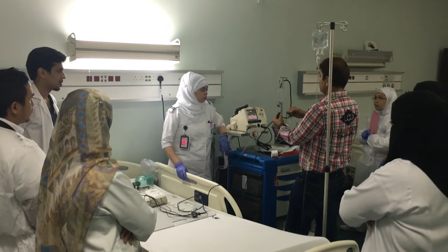To insert it maybe is okay, but to remove it, if somebody doesn't know, you will pull it and it will break, because there is a lock here to remove it. So why are we keeping it, if we are allowed to use the machine only in AED mode, why are we inserting this one? Leave this always, 24 hours, connected. This is the important thing which I have discussed there. Always 24 hours, leave it with the device.